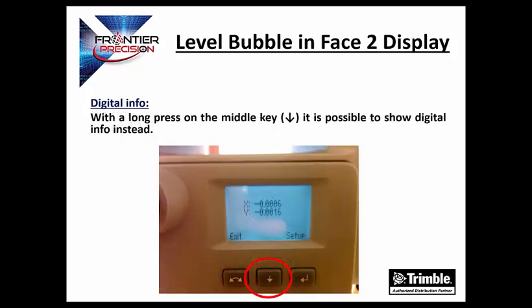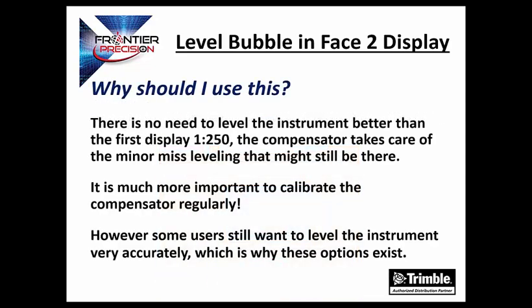If you press and hold down the middle down arrow key, it is also possible to show the digital info in a numerical value instead of the bubble. So the question is, why should I use this? Well, there's actually no need to level the instrument better than the first display of 1 to 250. The compensator, if it's properly calibrated, will actually take care of the minor misleveling that might still be there. It is much more important to calibrate the compensator regularly. However, some users will still want to level the instrument very accurately, which is why these options exist.